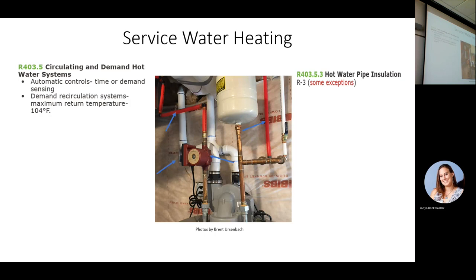So here's a recirculation loop, and I took this picture in a house, and actually it's done wrong, and I don't know how well you can see it. Well, they have the hot water heater. Here's the cold supply coming into the water heater. Here's our expansion tank. Here's our return line coming back. So when this pump runs, it runs hot water out through the whole loop and then returns back and goes down the dip tube on the water heater, and we just maintain hot water.